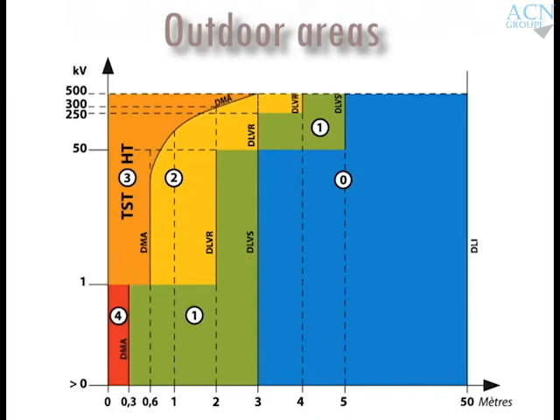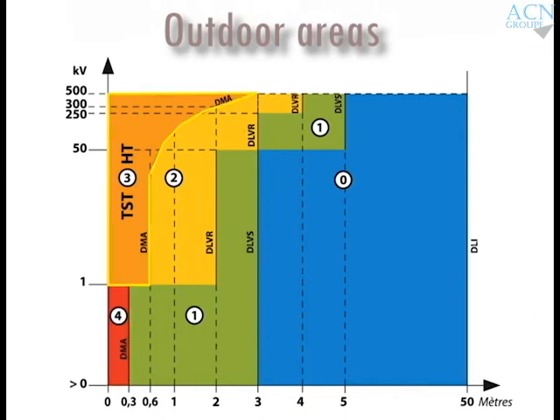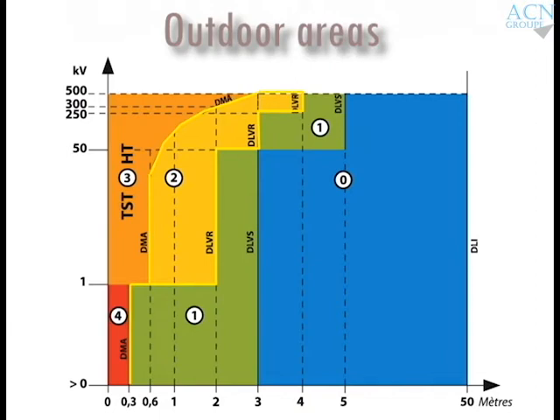Minimum Approach Distance (MAD): In low voltage, it sets the limit of Zone 1 and the whole of Zone 4, which means 0.3 meters from bare energized conductive components. In high voltage, Zone 3 up to the limit with Zone 2, it is fixed at 0.6 meters from the bare energized conductive components.